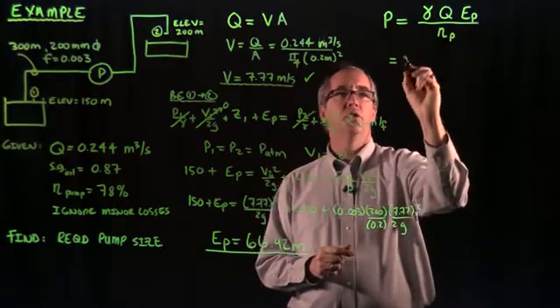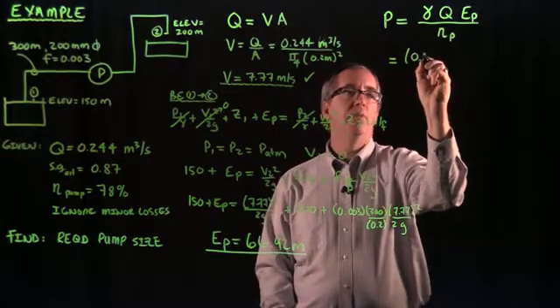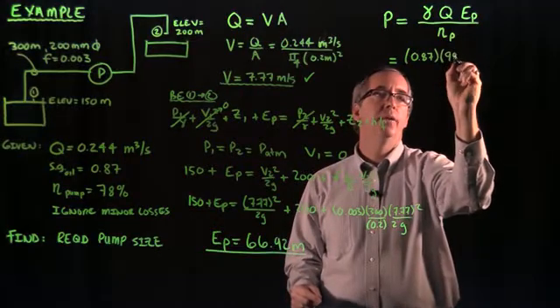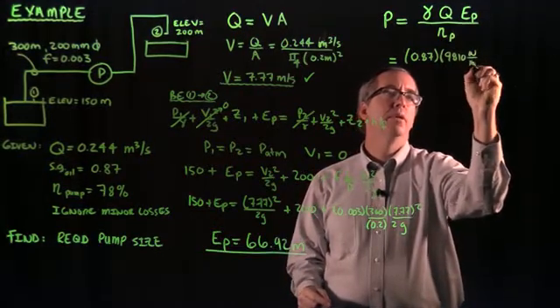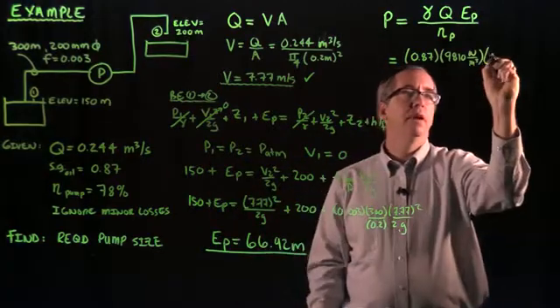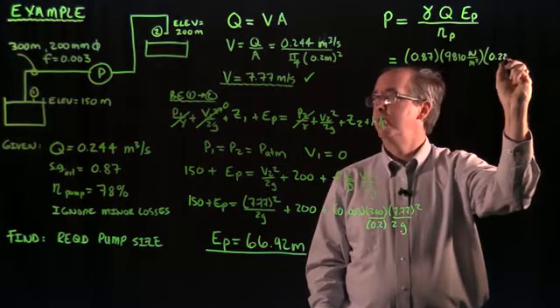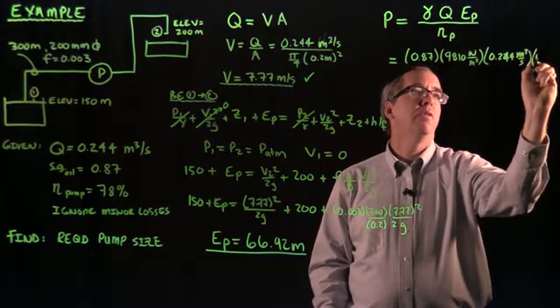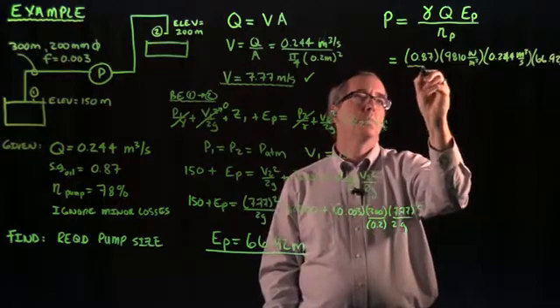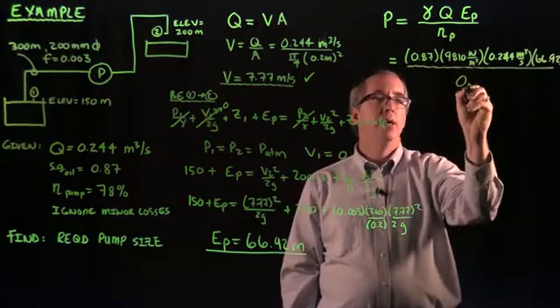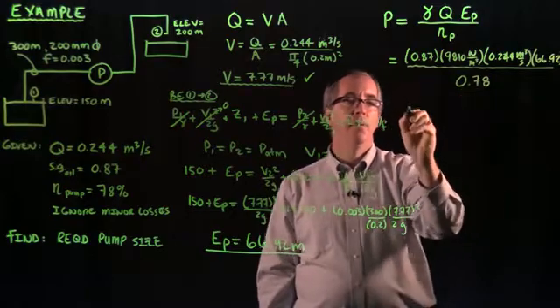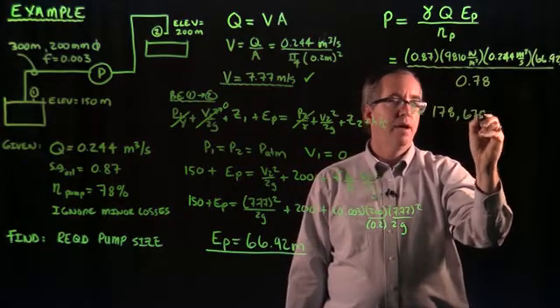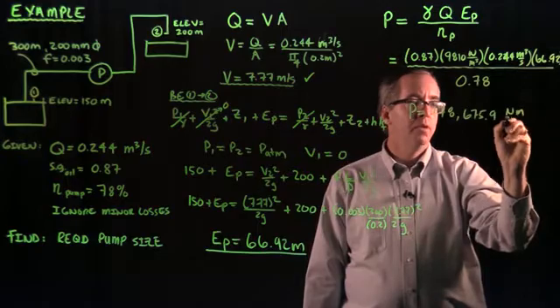So let's go ahead and substitute the terms in here. We've got oil, which has a specific weight of 0.87 times that of water. We're dealing with metrics, so that would be 9810, those are newtons per meter cubed. Our flow rate was given to us at 0.244 cubic meters per second. And then we just solved for that pump head at 66.92. We're going to divide that by 0.78, which is the efficiency of the pump. When we do that, we get 178,675.9 newton meters per second.